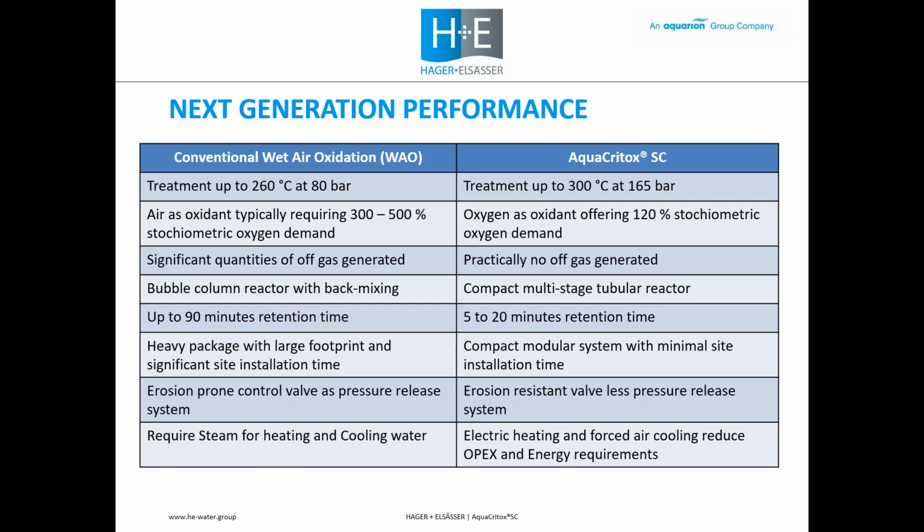And then we have the pressure letdown system. We use a tubular capillary kind of letdown system. A traditional wet air oxidation package would be dropping the pressure across a control valve. And this is an extreme service for a control valve, which typically leads to maintenance issues and the requirement for frequent change out of valve seats and associated items.